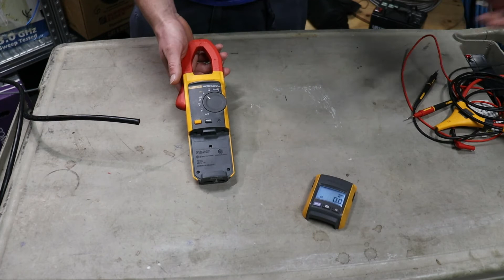Also, we'll talk a little bit now on amperage about the inrush. So these meters have the capability of seeing inrush current as overcurrent protection sees it, which is super helpful for anybody wanting to size their wire or know the FLA of a motor, the inrush current when you start it up, and how much they need to properly fuse so that it's not tripping all the time.